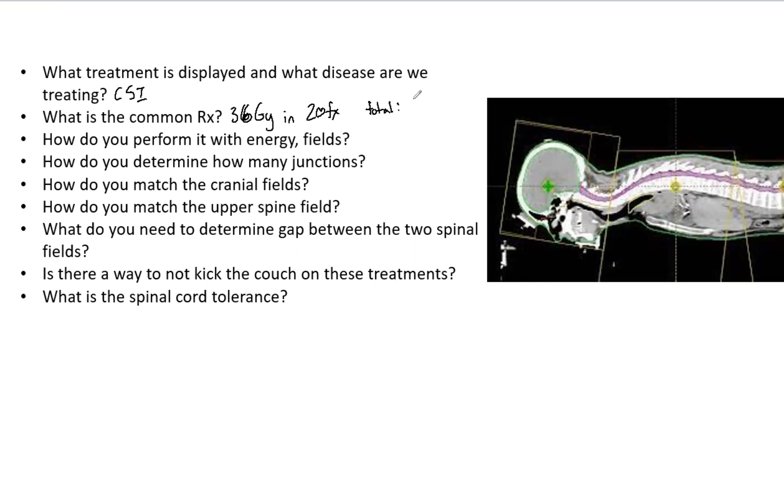How do you perform it with the energy and different fields? For the brain fields, you want to use 6X—essentially just like a normal 3D whole brain. For the spine, we want to dive and go a little deeper, so we're going to use for an adult 10 or 18X.